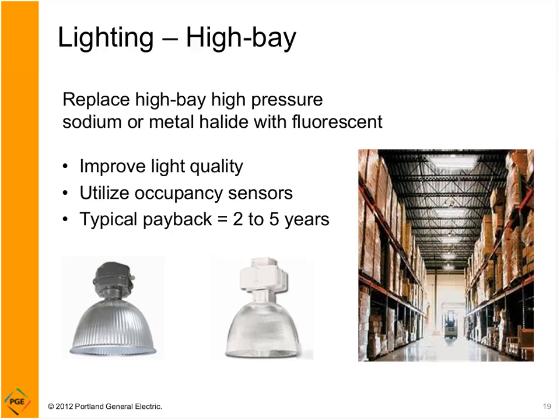You can utilize occupancy sensors. Anyone familiar with these metal halides or high pressure sodiums knows that they take about 5 minutes to get to full brightness, and occupancy sensors don't work real well with this type of fixture. With the fluorescent fixtures, you can have individually mounted occupancy sensors on each individual fixture. So, for example, if you were to walk down this aisle in this warehouse and the lights were off, the lights would turn on until you stopped, basically. As you walked under each one, they would be lit. And typical payback is in the 2 to 5 year range. Again, it's going to depend on hours of operation and so on, but generally it's a pretty cost-effective upgrade.